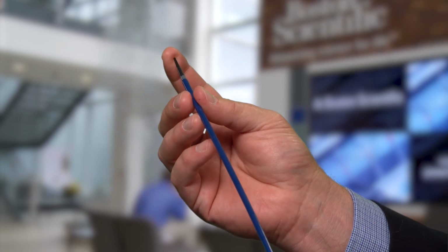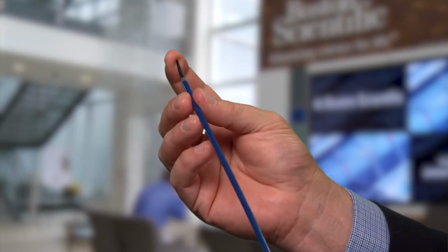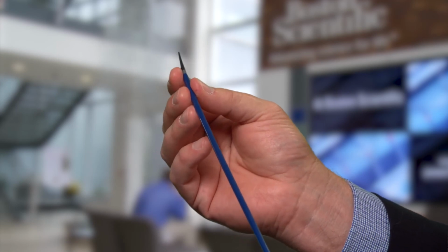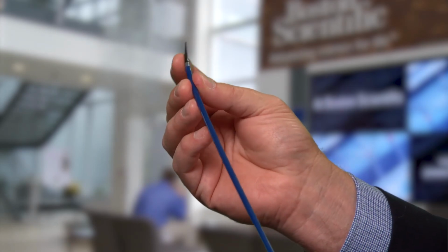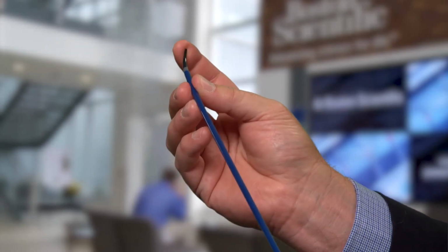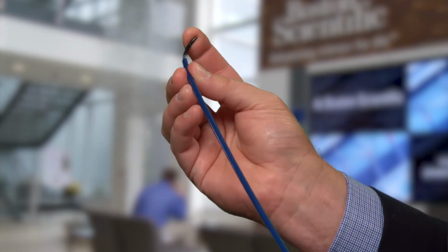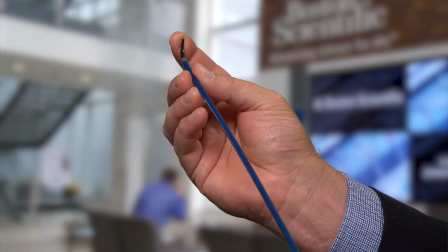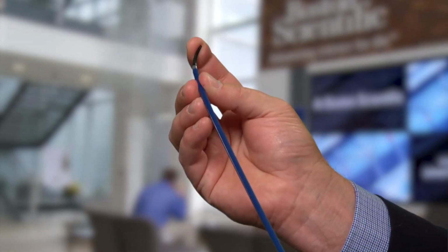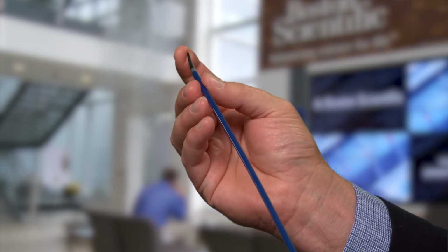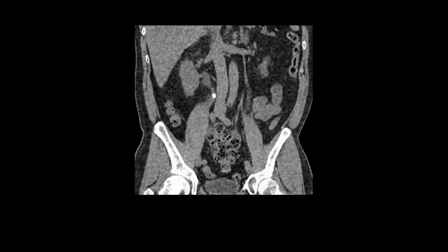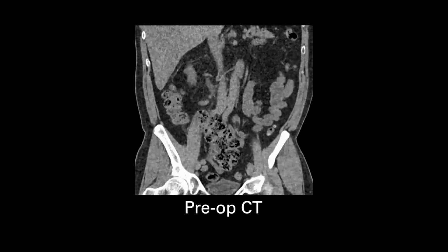With men, there sometimes can be an issue with placing the completely assembled access sheath, even though the obturator has gone in well. The obturator tends to be more flexible than the entire access sheath, and you can see how there's a bend portion right here, which can cause some kinking. So what occasionally will happen is a sheath that seemed to go in well won't track when you try to place it. At this point, it's important to look with fluoroscopy down at the bladder level. If you see this happening, a good strategy at that point is to place a super stiff wire, and at that point this should track up well.